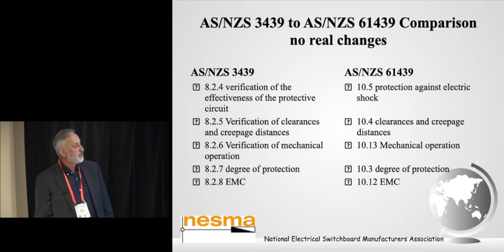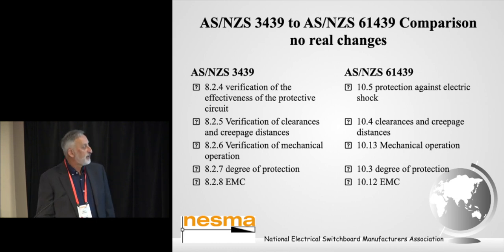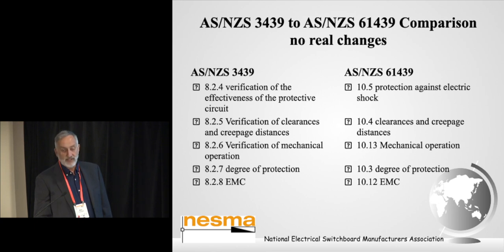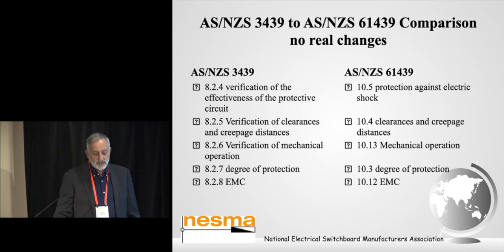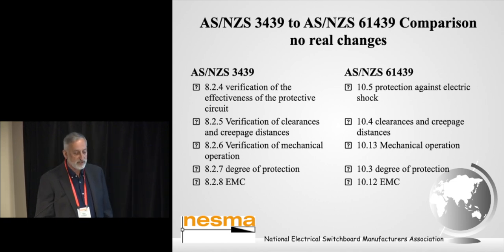Clause 10.5 under the 61439 is protection against electric shock, which is the old 3439 clause 8.2.4, the protective circuit verification. 10.4, creepage and clearance, which was the previous 8.2.5, verification of clearances and creepage distances. 10.13, mechanical operation, used to be the old 8.2.6. 10.3, degree of protection, was the old clause 8.2.7. And 10.12 under 61439 was the old 8.2.8. Under these clauses, we're seeing no real technical change, and so anything that's done in the previous 3439 is applicable in the 61439 series.